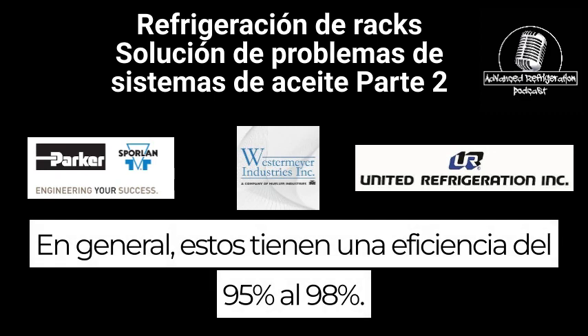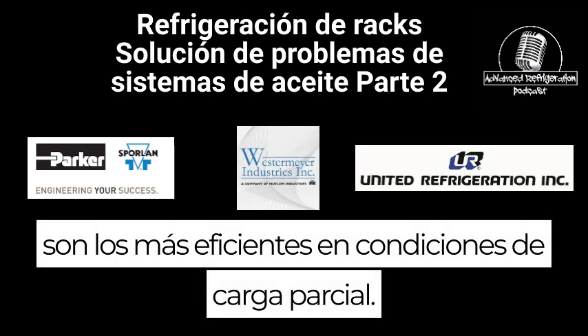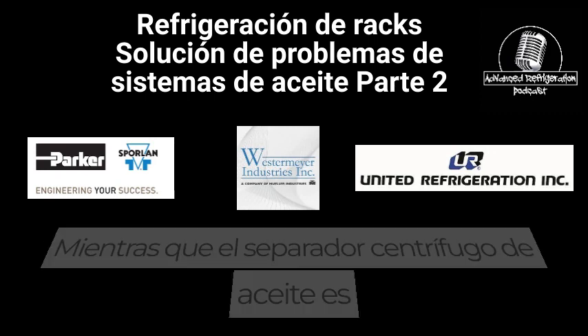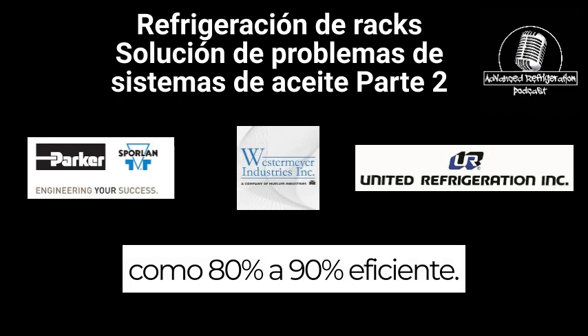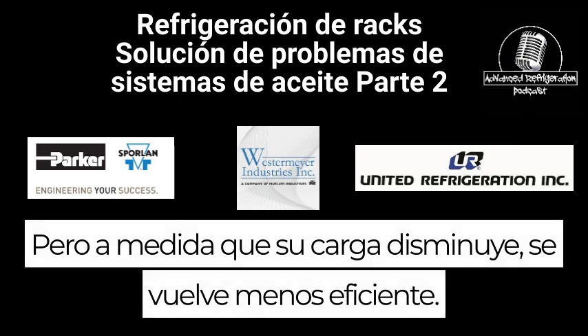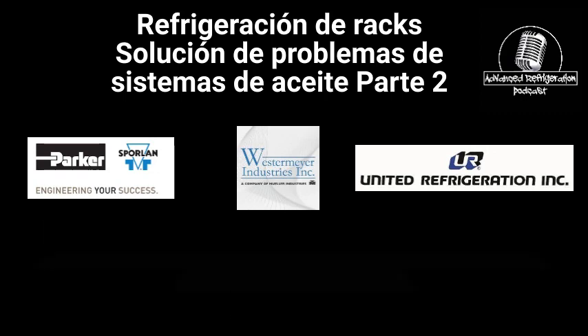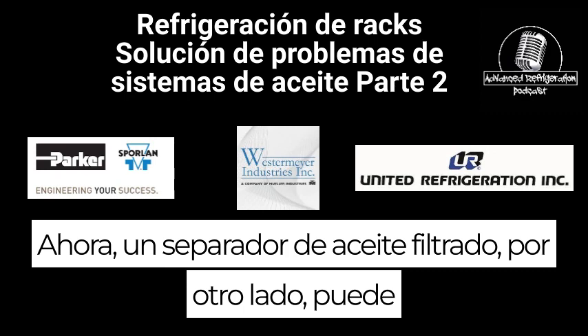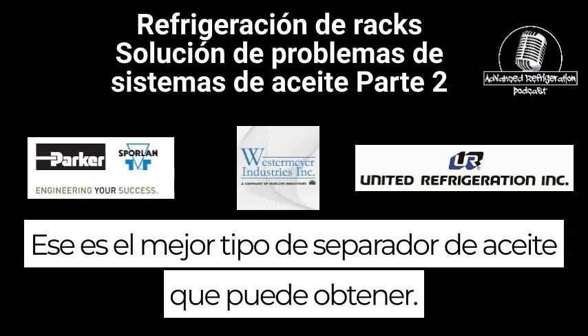Generally, these are about 95 to 98% efficient. They're the most efficient oil separators, and they are the most efficient under part load conditions. Whereas a centrifugal oil separator is like 80 to 90% efficient, but as your load drops off, it gets less efficient. So in the wintertime, when the head's floated way down, it's less efficient. A filtered oil separator, on the other hand, can handle those load changes much better with less load. So that is the best type of oil separator you can get.